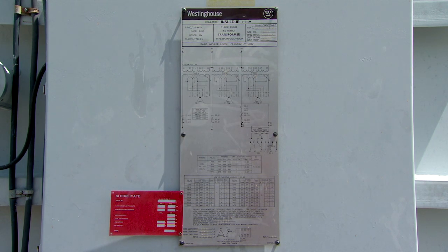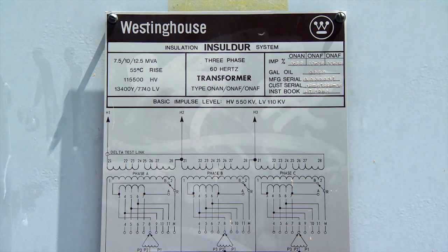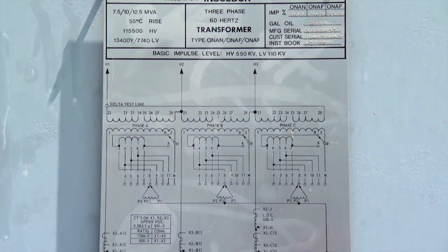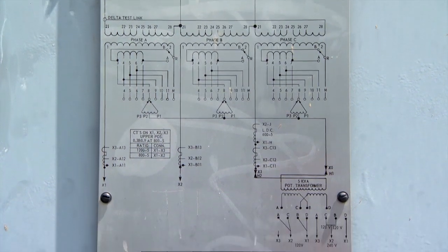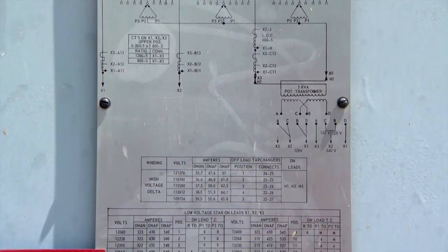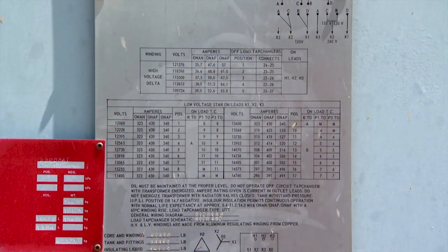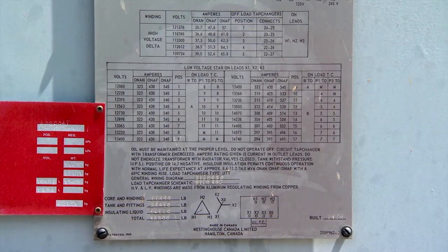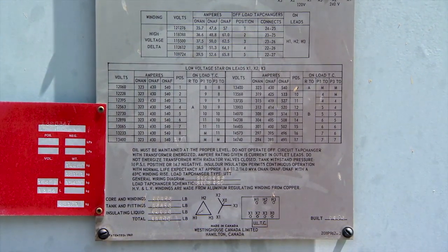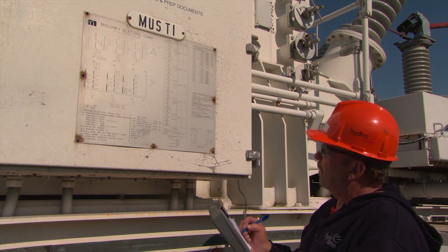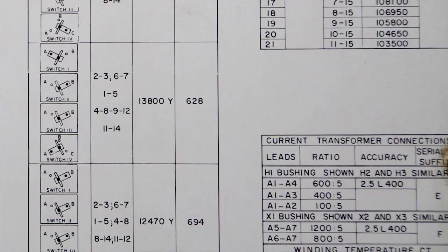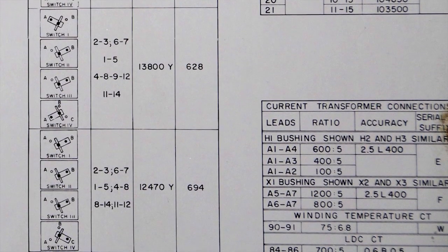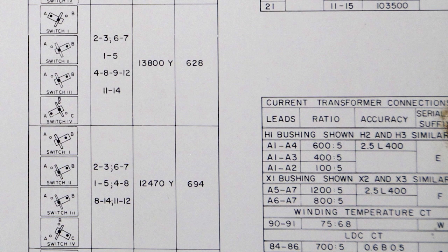In this case, we need a secondary voltage of 13,233 volts, which this mobile does not offer. The closest options are 13,800 volts or 12,470 volts. This means you need to first calculate the station transformer ratio and then calculate the MUS transformer ratio for both the 13,800 volt option and the 12,470 volt option.